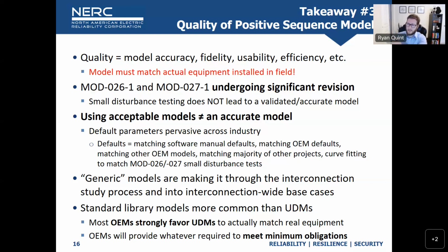Default, in my mind—and I'm trying to move quick here—default means matching exactly what's in the standard software package manuals, which you see very commonly. Matching the default OEM settings, meaning they weren't trued up at the time of commissioning. Matching other OEM models, of that same OEM or different OEMs. Matching a whole bunch of other plants nearby. Or, and this may not be a default, but parameter values that were simply curve fit and don't actually relate to any actual plant. We've heard from multiple sources that that's pretty common, done to meet compliance obligations for the interconnection process.